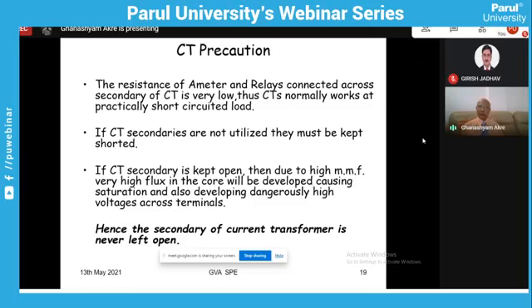It becomes a sort of power transformer or distribution transformer, having 1 turn in the primary and 100 turns in the secondary. So whatever voltage drop is there in the primary, 1 volt, 2 volt or 5 volt, will be amplified 100 times, and the secondary will appear at very high voltage. So depending upon the transformer, dangerously high voltages are developed across the secondary, and that can give a shock to the operators, or it can damage the transformer, and it can saturate the core permanently also. So thereby the full transformer can become useless.